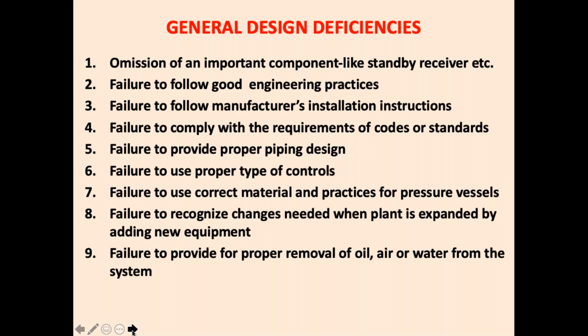I will tell you one accident when a person was trying to open the valve in the liquid line for starting. The whole coupling, which is welded to the receiver at the bottom, came off because the welding was not properly done. With the result that nothing could be done, there was no standby equipment available, till the entire ammonia leaked from the receiver. My God, it was a horrible thing. People had to suffer a lot. So it is very, very important that we do proper welding and have a standby so that we can always pump down in case one receiver starts leaking.